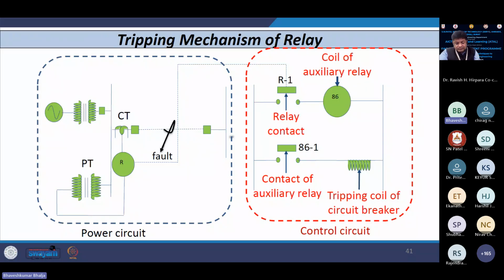So then what are they using? Utility people are using single phase auto reclosers, right? They are using auto reclosing devices. The auto reclosing device is a part of this circuit breaker here. Let's say it is also here at the other end, but let us concentrate on the sending end. So whenever a fault occurs here on the line, this relay is going to sense the fault. It gives a signal from here to its contact.